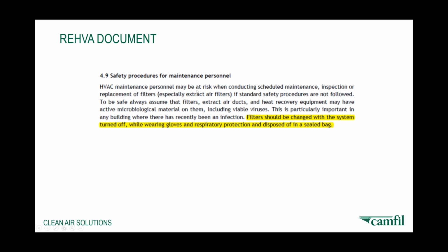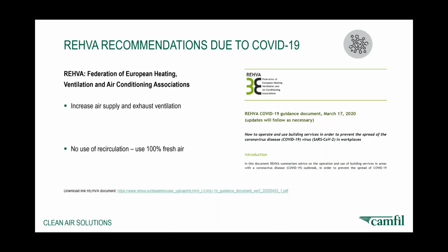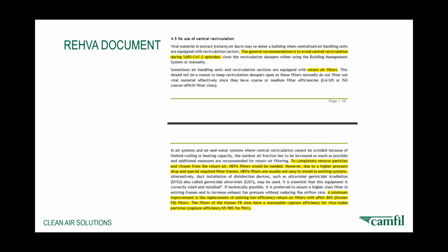And then on exhaust and return air, as we said originally, on March 17th, they said no use of recirculation. They understood this was difficult to completely change or upgrade a system and remove the full recirc. So they're recommending now that you avoid central recirculation, but if your recirculation section is equipped with return air filters, you should upgrade them. So to completely remove particles, return air HEPA filters perhaps will be needed, but we're all aware that an HVAC system is designed to operate at a fairly low pressure. The filters that are used typically operate at about maybe 60 to 120 pascals, maybe as high as 250 in some cases. But the pressure drops, or the pressure across filters, tend to be quite low in these systems.